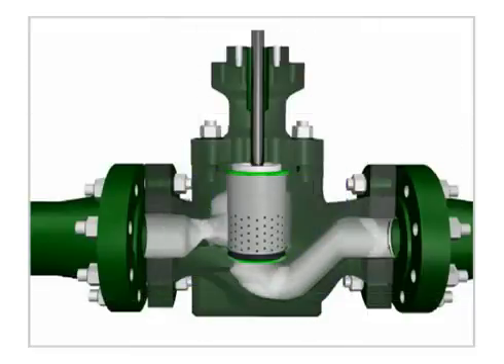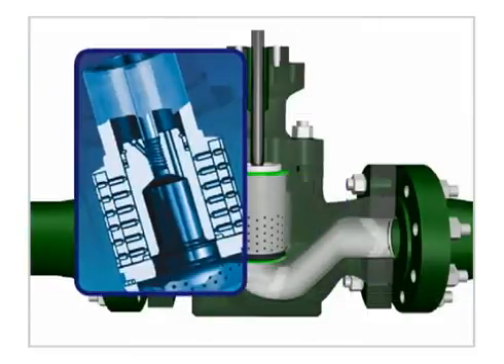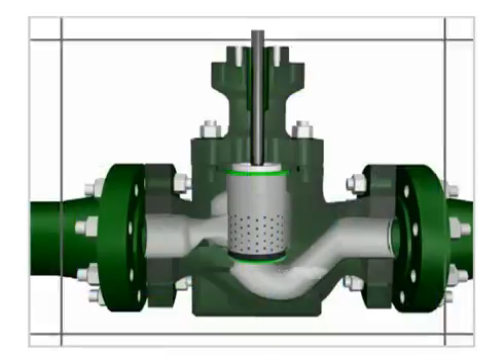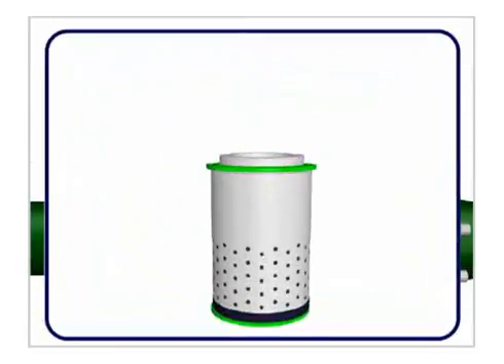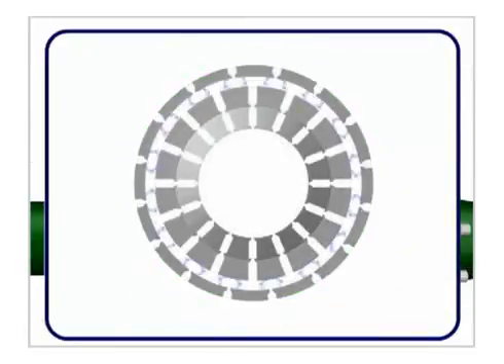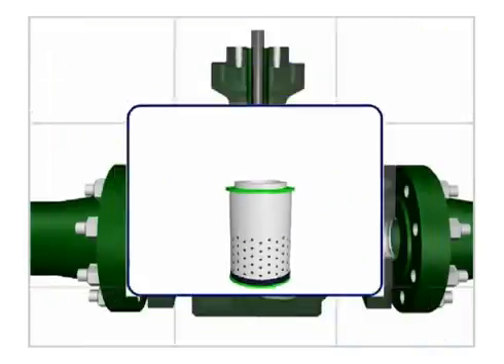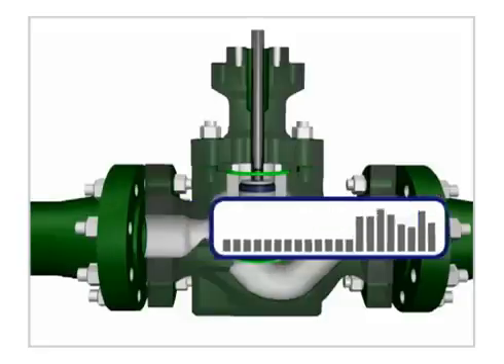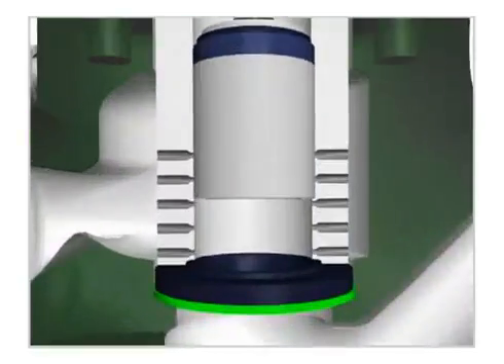Pressure drops are staged by the use of expanding nozzles or expanding flow areas. For example, in the Cavitrol III valve trim, nozzles have holes shaped to manage flow separation. Multiple small holes shift the noise to higher frequencies. Cavitation is isolated by directing fluid into the center of the valve using a flow down orientation so bubbles implode away from the valve components.